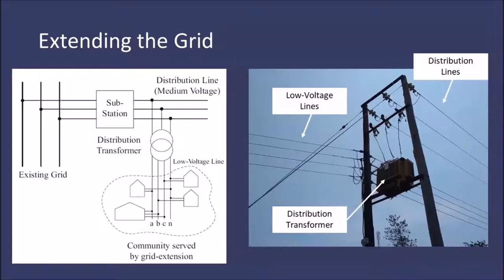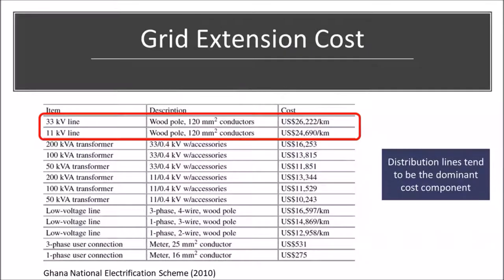It turns out distribution lines are really important for grid extension - they're the most costly aspect of it. Here are some numbers I pulled from the Ghana National Electrification Scheme, showing distribution line costs of somewhere between $20,000 and $30,000 a kilometer. For communities that are 5, 10, 15, 25, or even further away, the distribution lines can be 80 or 90% of the total cost.